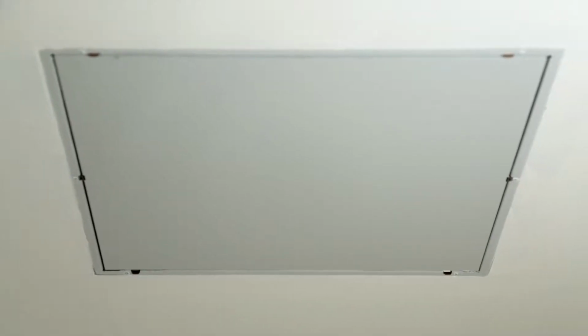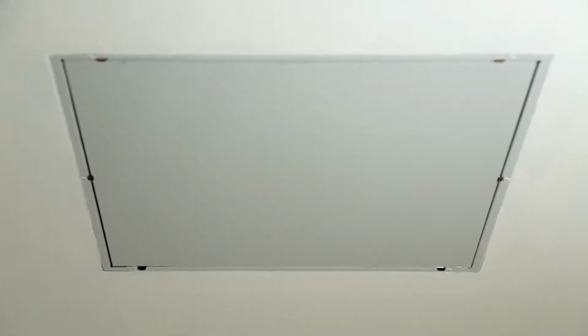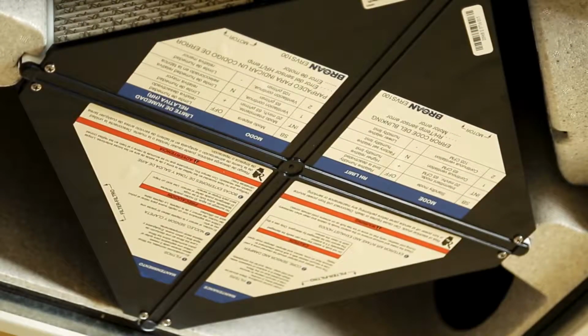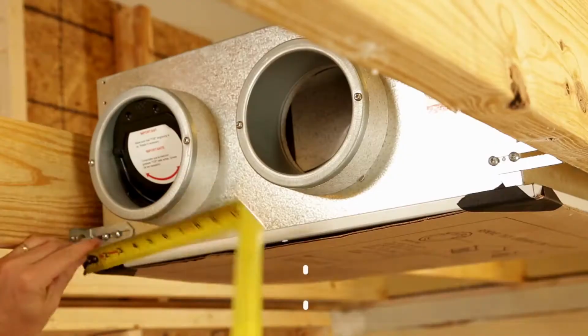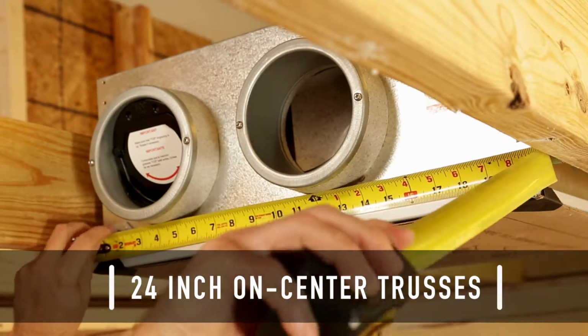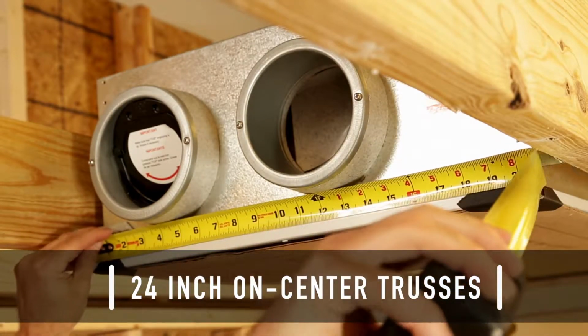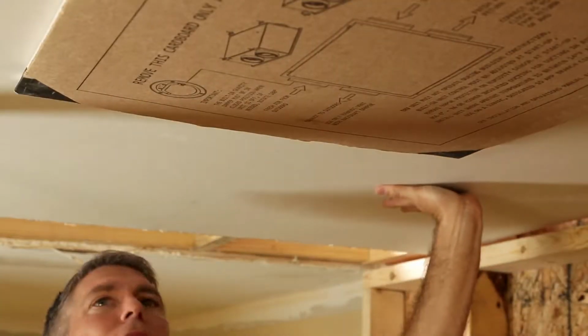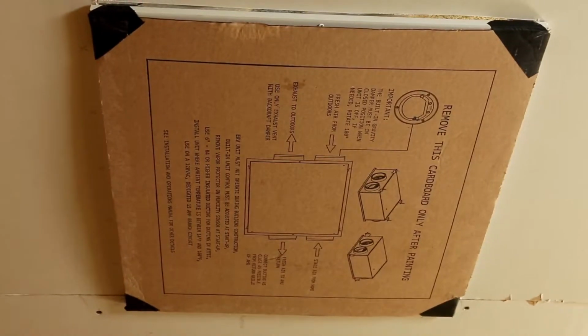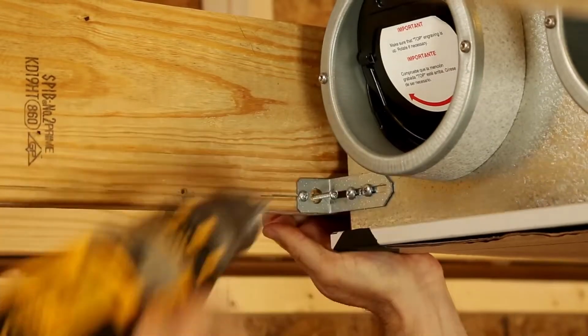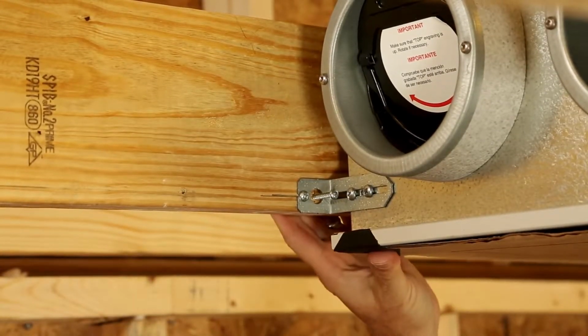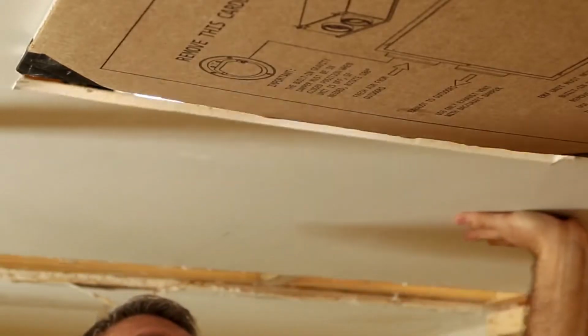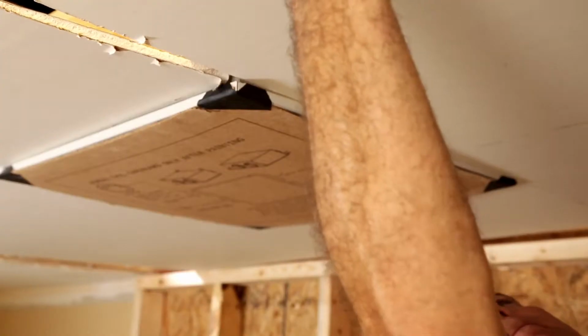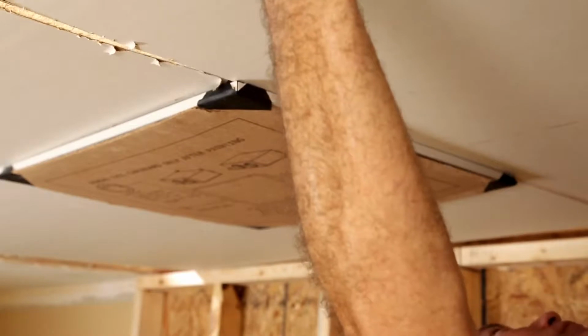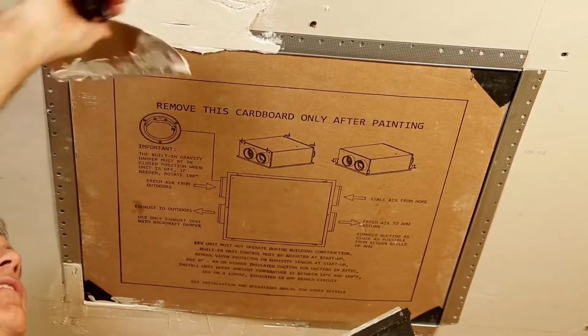Mounting the ERVS100 in the ceiling makes it easy for homeowners to perform system maintenance from within the living space. When mounted in the ceiling, the system is installed between 24-inch on-center trusses. The ERVS100 is designed for optimal installation during the construction phase of a home. Install between trusses prior to the installation of drywall on the ceiling. When installing in the ceiling, the ERVS100 can be installed with the unit's cover overlapping the drywall as a flange, or with the unit's cover flush with the ceiling material.